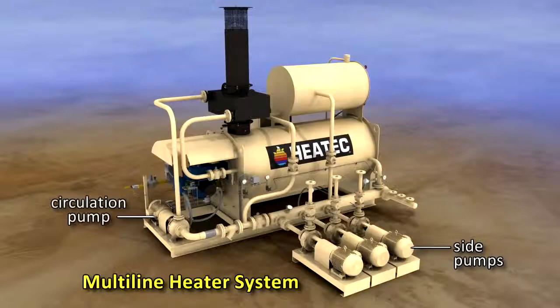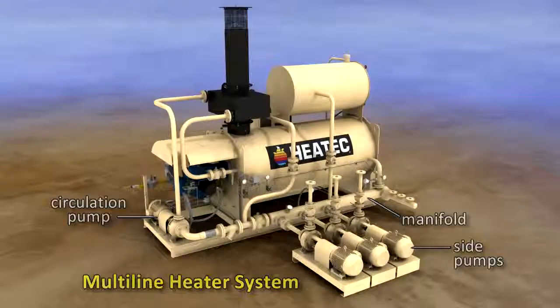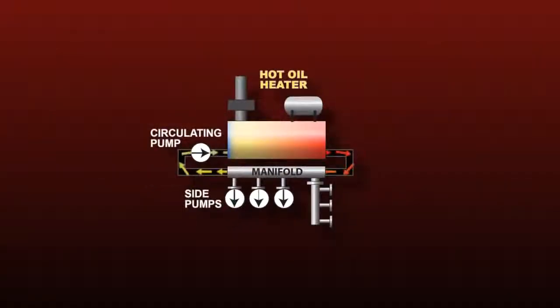The multi-line heater has a circulation pump and manifold. The circulation pump serves solely to recirculate the oil through the heater coil.